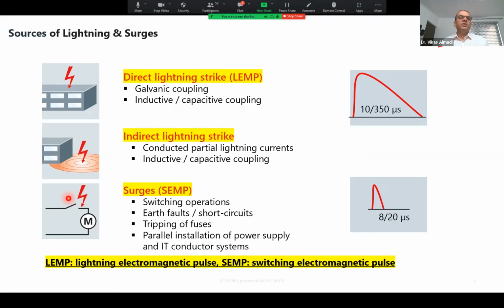Switching on of motors, short circuit faults, earth faults, tripping of even the fuses, and parallel installation of power supply and IT conductor systems. IT is your information technology I'm talking about, not the IT system of electricity. All these systems form kind of loops, and the current flowing in these loops causes the surges. And the switching effect itself is a kind of absorbing and releasing of energy that also appears in the form of surges. So some are big surges, some are small surges.